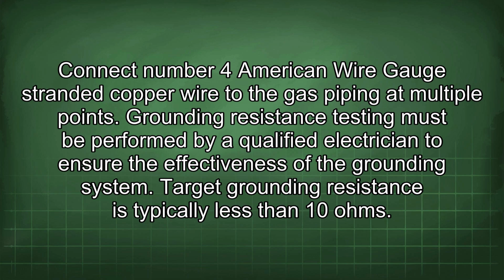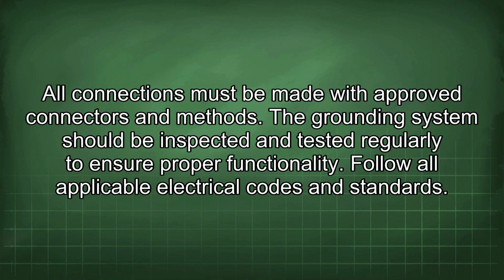Grounding resistance testing must be performed by a qualified electrician to ensure the effectiveness of the grounding system. Target grounding resistance is typically less than 10 ohms. All connections must be made with approved connectors and methods. The grounding system should be inspected and tested regularly to ensure proper functionality. Follow all applicable electrical codes and standards.